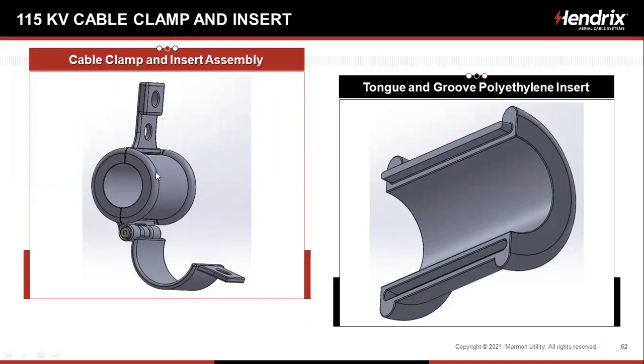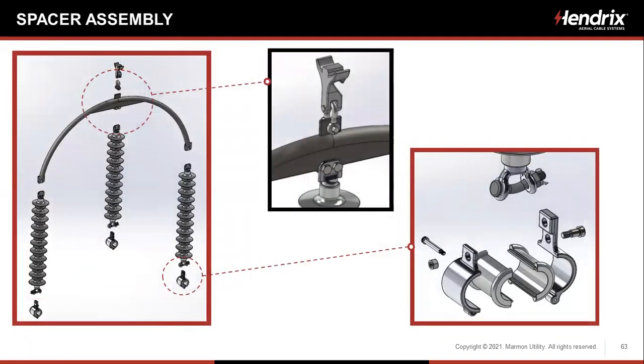The cable clamp and insert assembly basically has a high density polyethylene sleeve that's going around the conductor before it gets into the clamp. And that sleeve is going to smooth out the voltage gradient, give us more insulation at that connection point. The spacer assembly itself is these parts. And you can see you have an extra degree of freedom at the messenger connection and at the cable connection, okay?